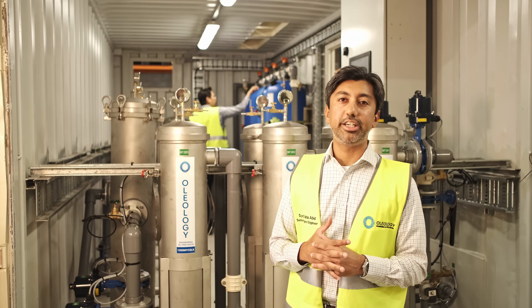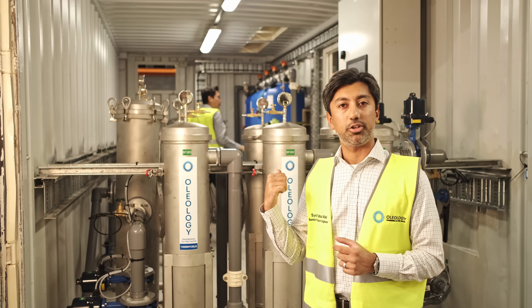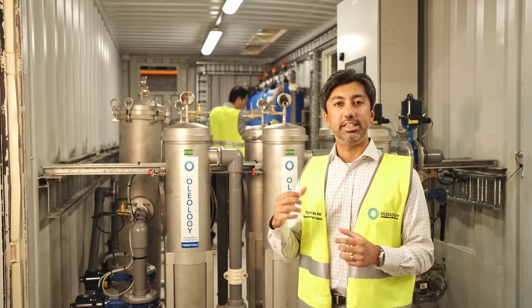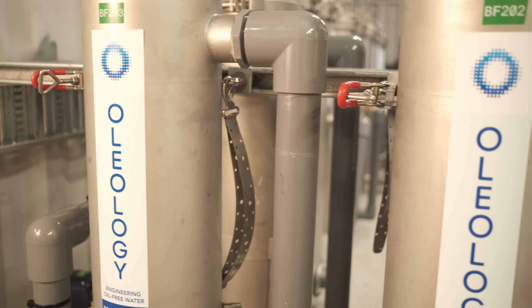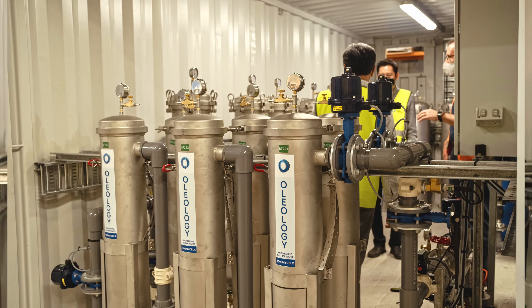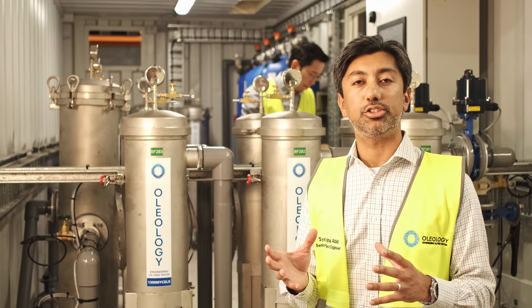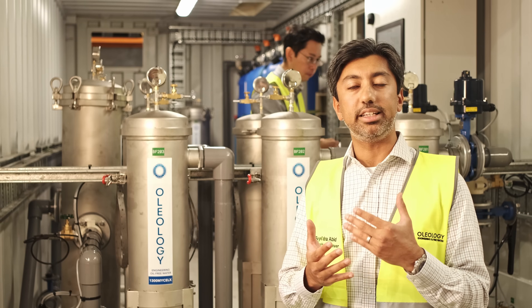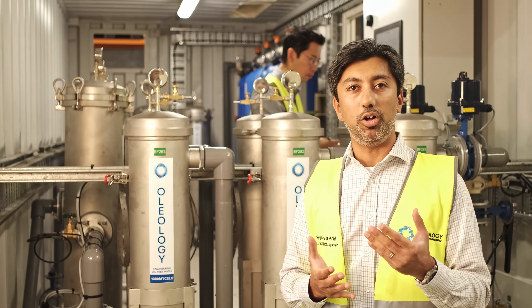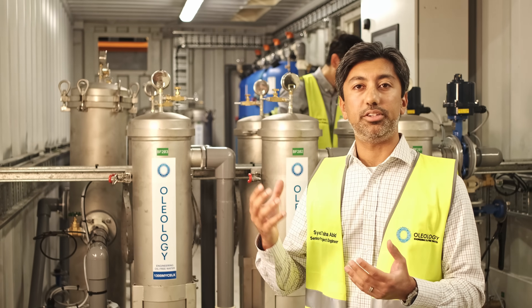The way Oleology does their treatment system — right behind me as you can see, we've got these six filters. These are the bag filters; their predominant function is to catch all the debris and protect the filters which are downstream. That is where the actual filtration — in terms of removing the hydrocarbons, all things like BTEX as well as PFAS — happens sequentially.